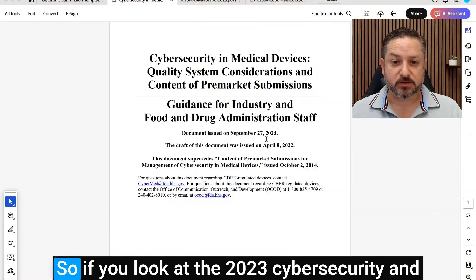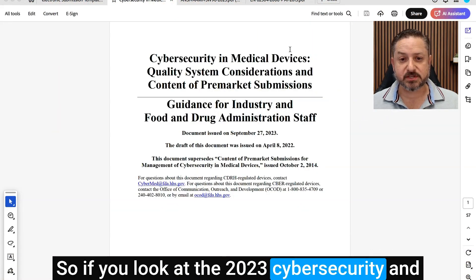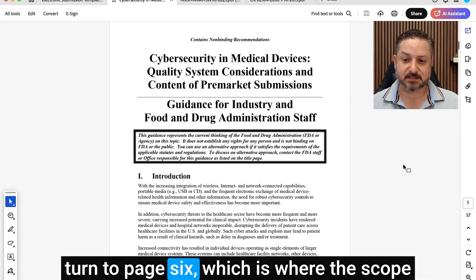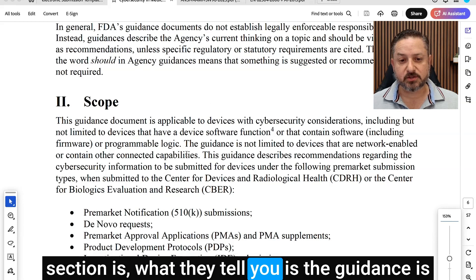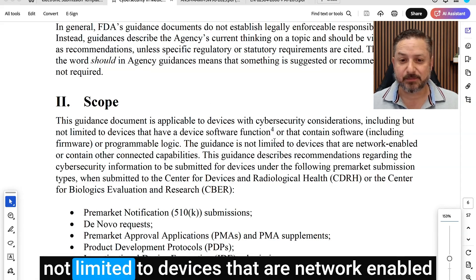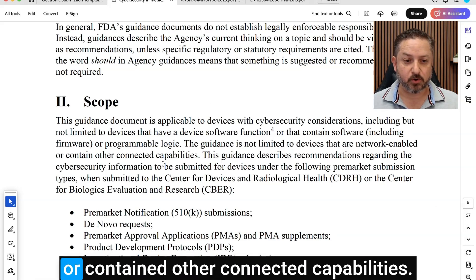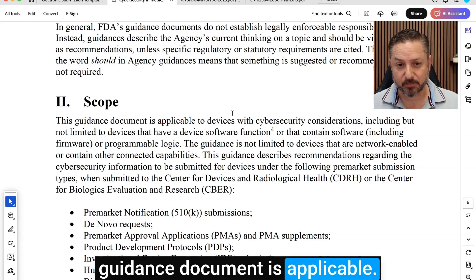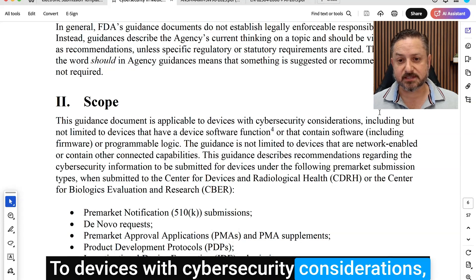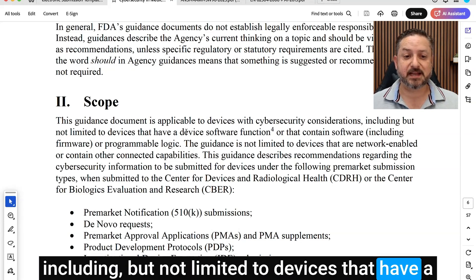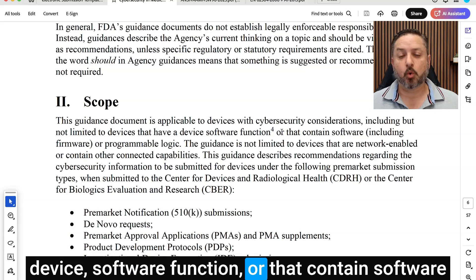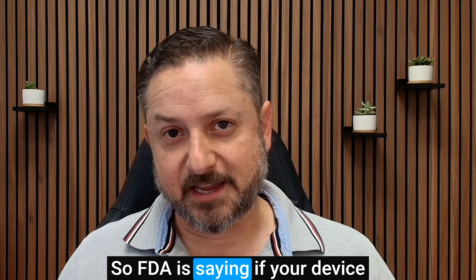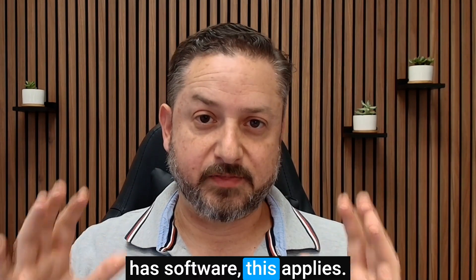And if you don't believe me, I'm going to show you. If you look at the 2023 Cybersecurity and Medical Devices Guidance Document and turn to page 6, which is where the scope section is, what they tell you is the guidance is not limited to devices that are network-enabled or contain other connected capabilities. What it says is this guidance document is applicable to devices with cybersecurity considerations, including but not limited to devices that have a device software function, or that contain software, including firmware, or programmable logic. So FDA is saying if your device has software, this applies.